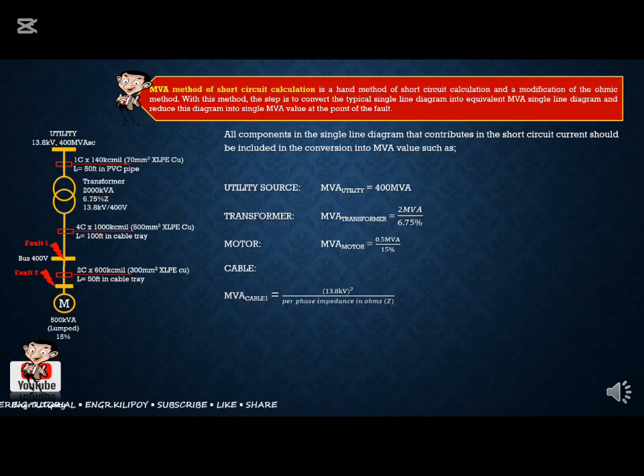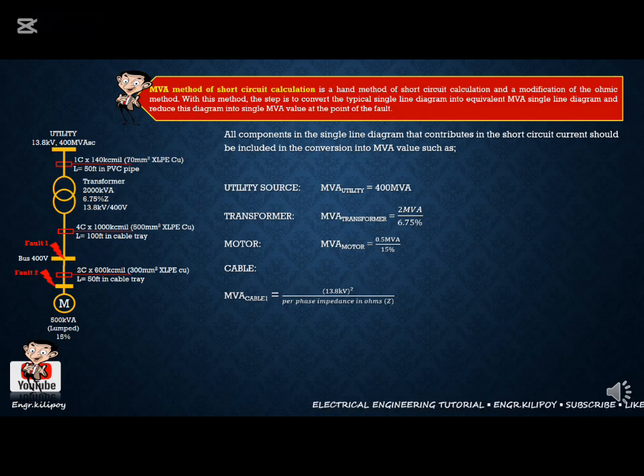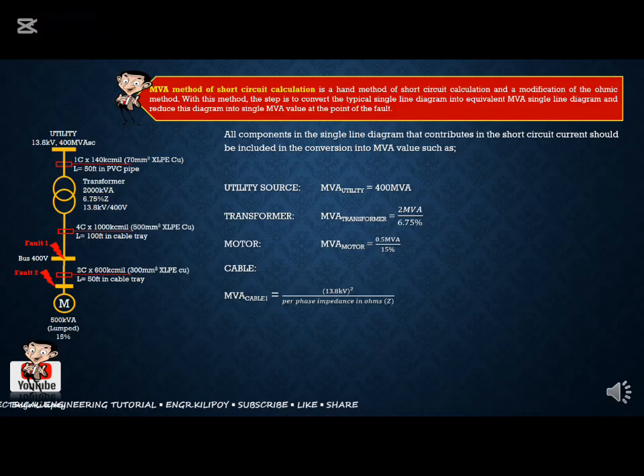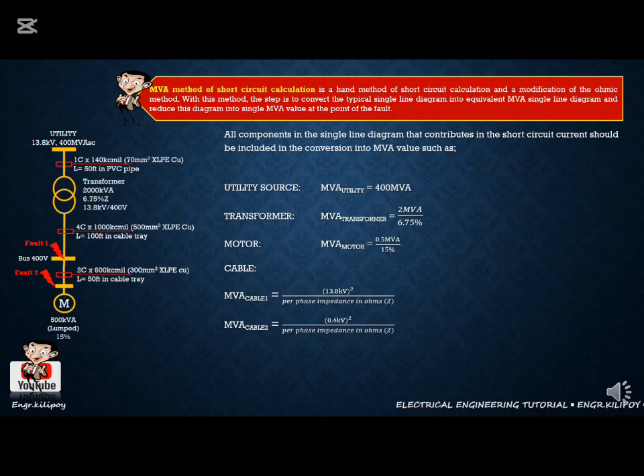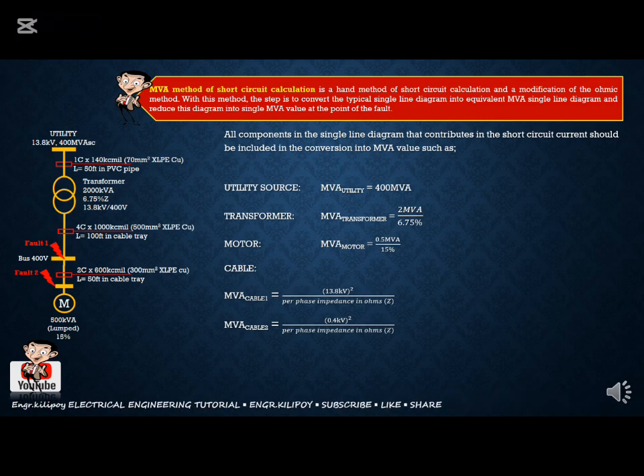For the cable, this is the formula. For cable 1, since this is 13.8 kV, ang voltage natin dyan is 13.8 kV squared over the per phase impedance in ohms of 140 kcmil, 1 core per phase at the length of 50 feet. For cable 2, same. In this case, 0.4 kV kasi ang bus voltage dito is 400 volts, over the per phase impedance of 1000 kcmil with 4 cores per phase with the length of 100 feet.